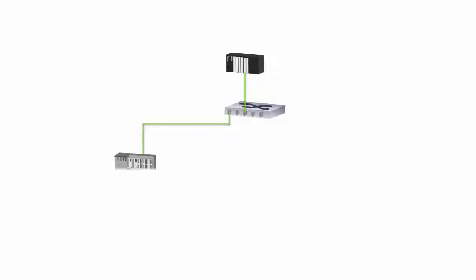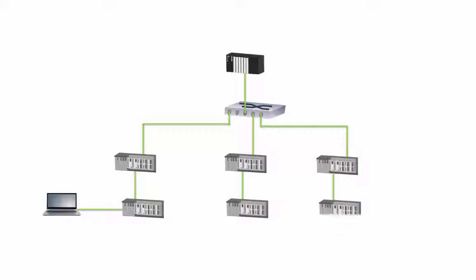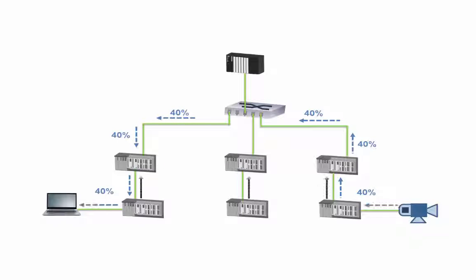PROFINET is an Ethernet-based communication protocol. Participants communicate in parallel and independent from each other. PROFINET uses a switched medium with 100 Mbit full duplex, so identical information is therefore only available from point to point.